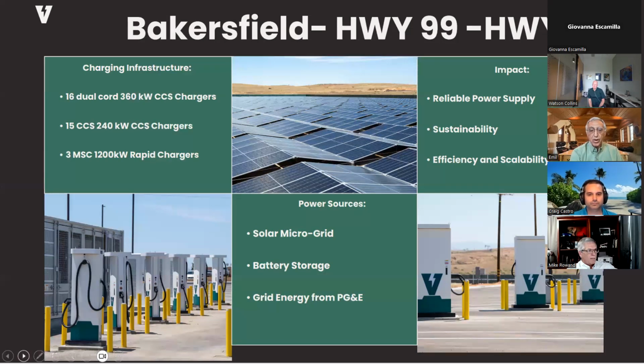The power between those 240 kilowatt chargers and the MCS chargers is shared. We have power conversion modules that convert 480 volt three-phase AC into DC, and that power is shared between CCS and MCS. That was part of our decision to ensure we have a path forward for future-proofing our development, with a migration path from CCS to MCS.